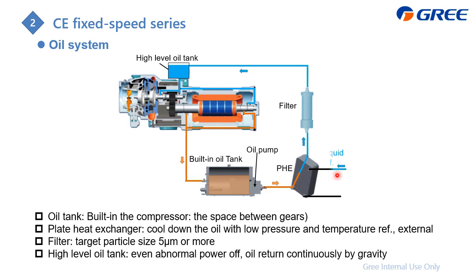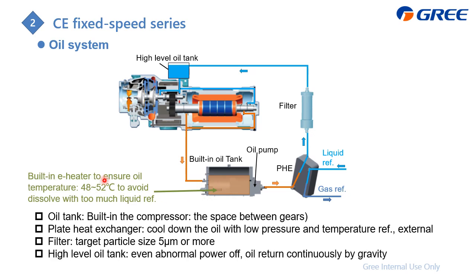As for the refrigerant, here it is liquid, and when it goes through, it becomes hot, which cools down the oil, and the refrigerant becomes gas. And here there is also a built-in e-heater to keep the oil temperature at 48 to 52 degrees. If the oil is too cold, it will dissolve too much liquid refrigerant, right? So we need to ensure the temperature of the oil is not that cold.